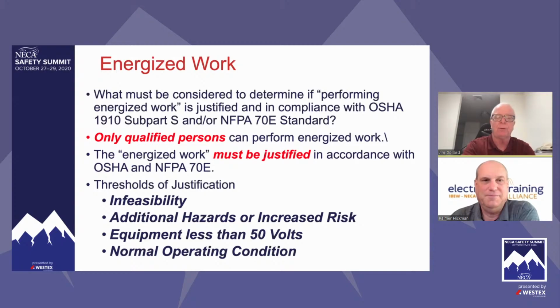If an individual, you could have a journeyman wireman with 30 years experience on the job. The only way that the employer is going to be able to make a determination that wireman is qualified to perform justified energized work is if they're trained in accordance with NFPA 70E. They follow all of those rules. They're trained on the test instrument that they're going to use, and they can do a shock and arc flash risk assessment. Palmer spoke briefly about some of the thresholds there, infeasibility.